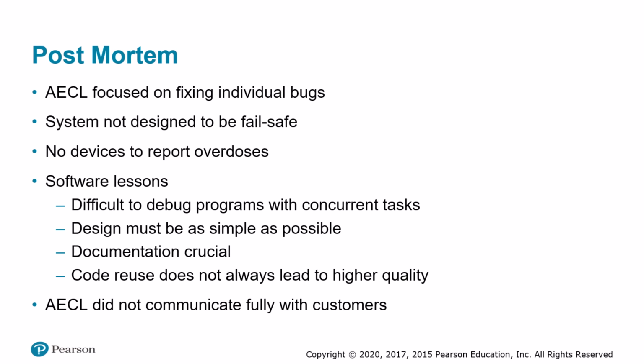That was their first mistake because such an approach was too narrow, because the entire system was broken, not just the software. The real problem was that the system was not designed to be fail-safe. Good engineering practice dictates that a system should be designed so that no single point of failure leads to a catastrophe. And by relying completely upon software for protection against overdoses, the Therac-25 designers ignored this fundamental engineering principle. And another flaw in the design of the Therac-25 was its lack of software or hardware devices to detect and report overdoses and shut down the accelerator immediately. Instead, the Therac-25 designers left it up to the patients to report when they had received overdoses.